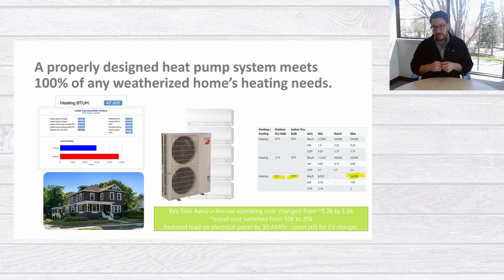I want to highlight some key takeaways. Number 1, if a home needs 108,000 BTUs per hour versus 47,000 BTUs per hour, all of your operating costs, your heating expenditures, are also going to be at a level 2x what the home would now be performing at. Another takeaway is that the install cost is going to be 2 times more expensive. So with this type of a heat pump project with 1 outdoor unit, 5 indoor units, supplying 100% of the heat load, that type of a project ranges somewhere around $20,000 to $25,000. Well, if we were doubling the amount of equipment, now it's a $40,000 or $50,000 project.